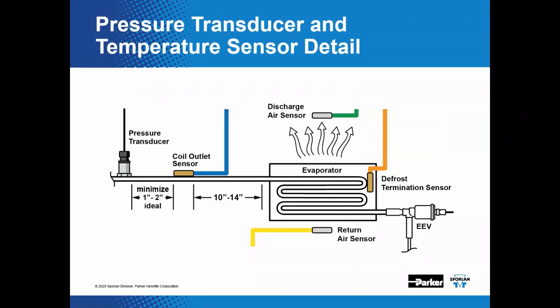Here's a detailed view depicting recommended temperature sensor and pressure transducer locations with the suggested spacing between the components. Here you can see the pressure transducer and the various temperature sensors for things like coil outlet, discharge air, return air, defrost termination, and you can see the assigned color coding that Sporlan has decided to use for these devices. And you can see the spacing, like we're depicting 1 to 2 inches here between the pressure transducer and the coil outlet sensor, and then 10 to 14 inches away from the surface of the evaporator coil itself for this particular one. Correct. There are more details, of course, in application and product bulletins on these.